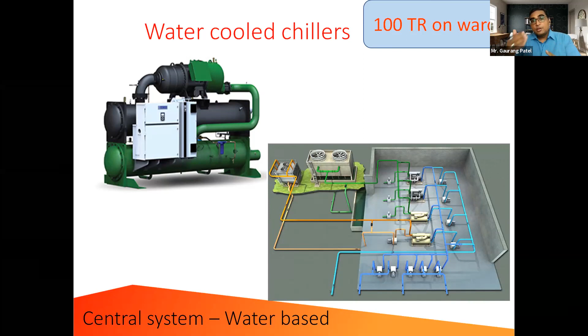Now this is a brief comparison between them, but I am not going into that part right now. I will just give you two parameters here. One is the efficiency. With a centralized air conditioning system, you are able to get a power rating of 1 to 1.2 kilowatt per ton. When I say centralized air conditioning system, I mean your VRF systems, your air cooled chiller systems, your water cooled chiller systems. They consume 1 to 1.2 kilowatt per ton, and split ACs normally consume 1.3 to 1.4 kilowatt per ton. So that is almost 20 to 25% higher than the central air conditioning system.